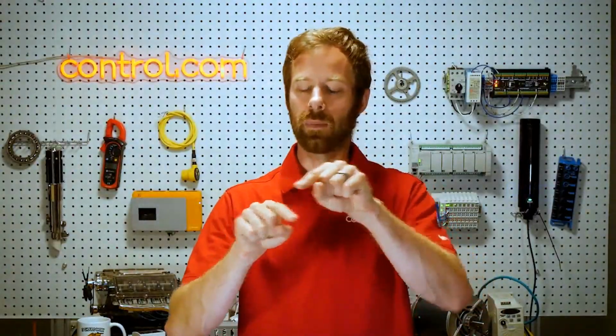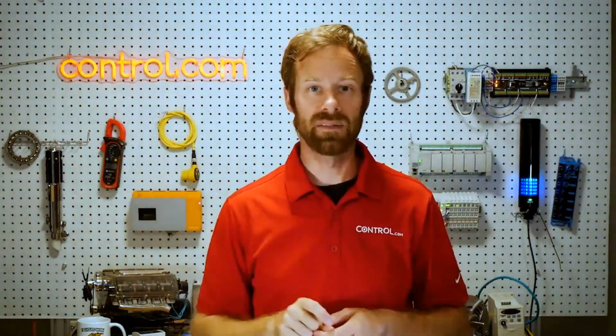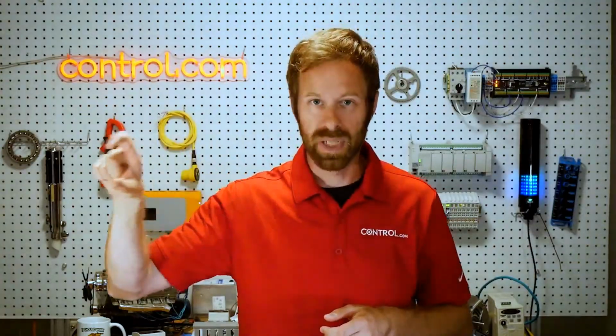What was the reason for that? But if we have 2 wires being compared against each other, the difference between them, and they travel past this machine, they're both going to see an equal spike at the same time. But the difference between them has stayed the same. So we know that that was due to some external interference, and by the time it reaches the PLC, the end device, there is still no difference between the wires. The only differences would be caused by the original sensor outputting a difference between the voltages. So it's a really clever, creative way to minimize some of the electromagnetic interference.